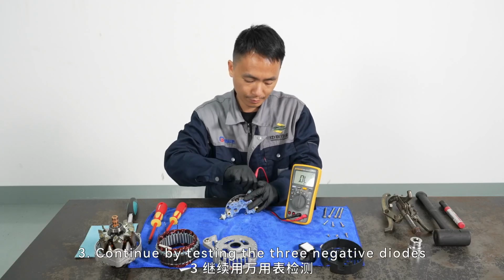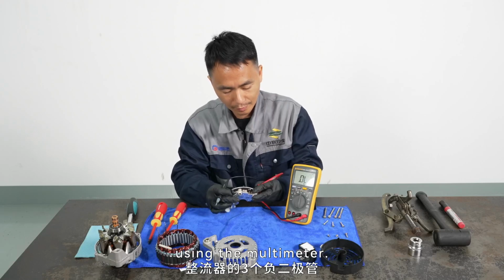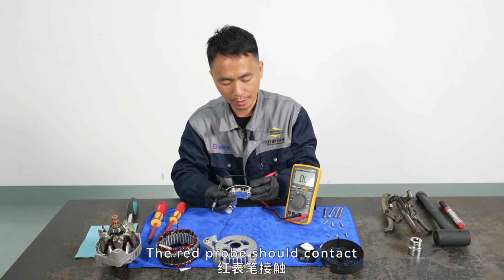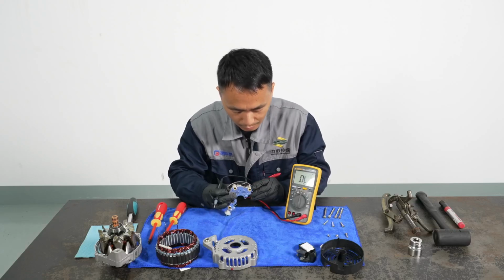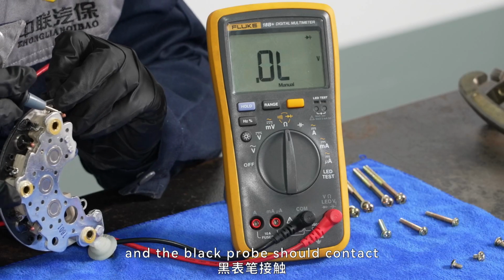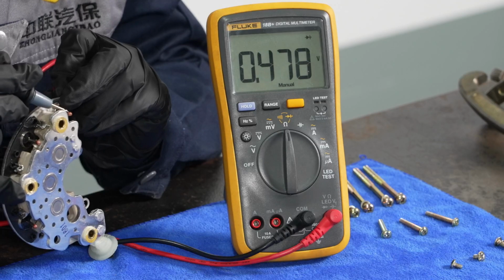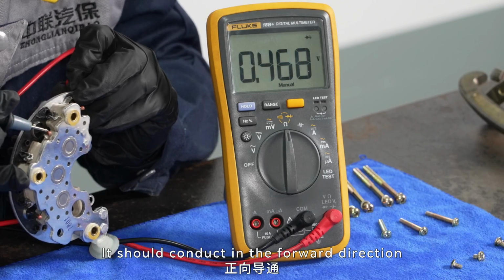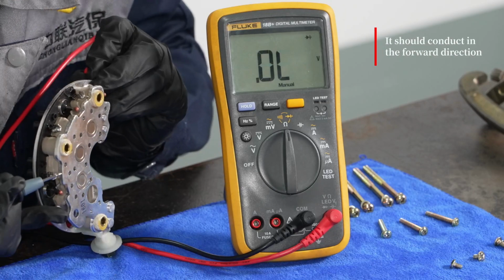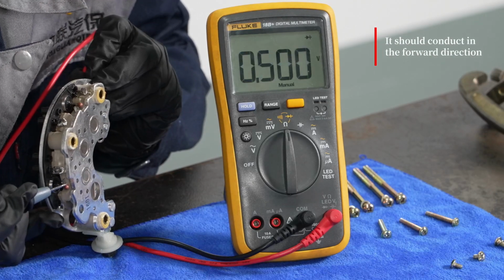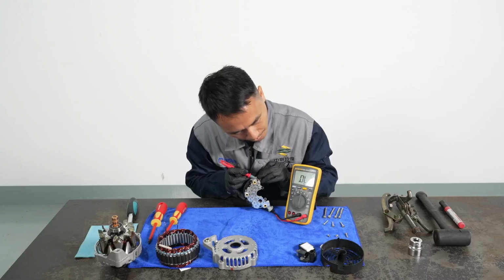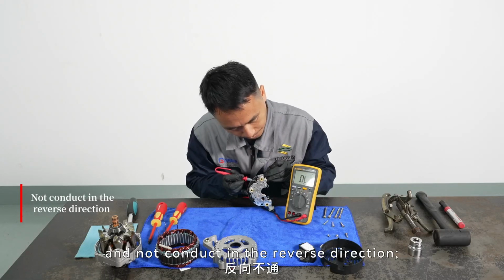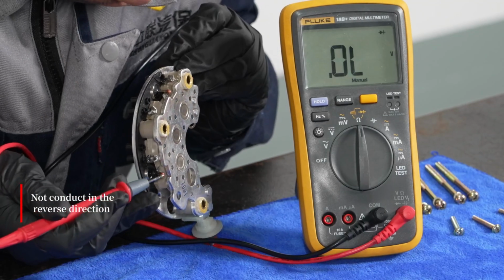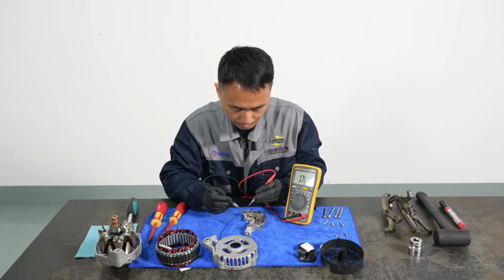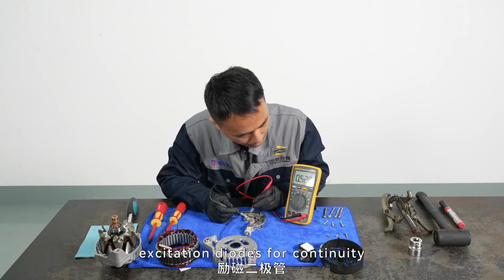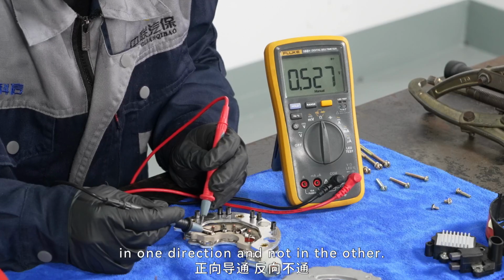3. Continue by testing the 3 negative diodes using the multimeter. The red probe should contact the negative rectifier plate, and the black probe should contact the negative diode terminals. It should conduct in the forward direction and not conduct in the reverse direction. 4. Check the 3 excitation diodes for continuity in one direction and not in the other.